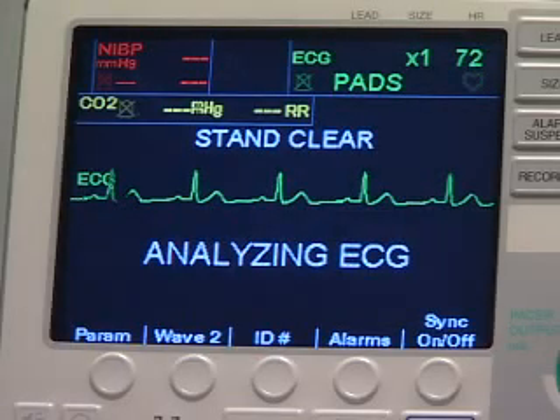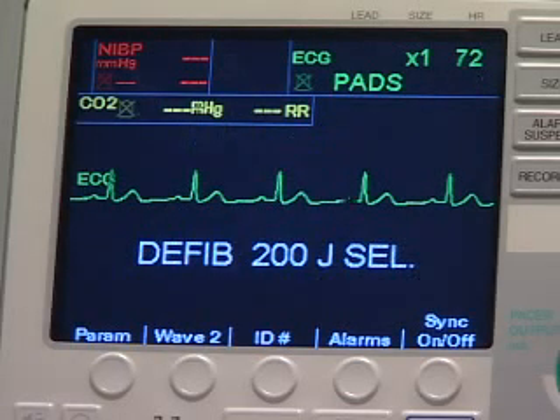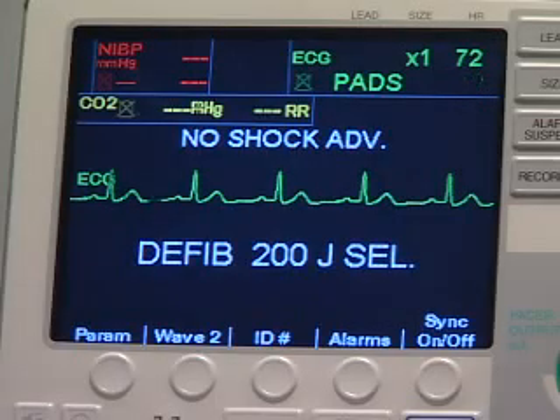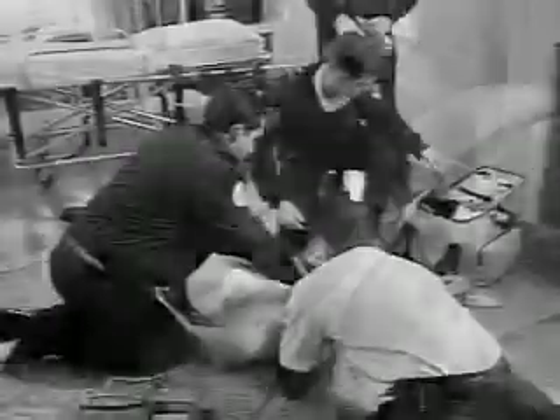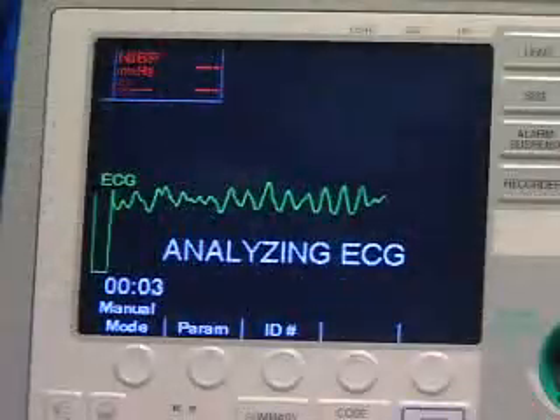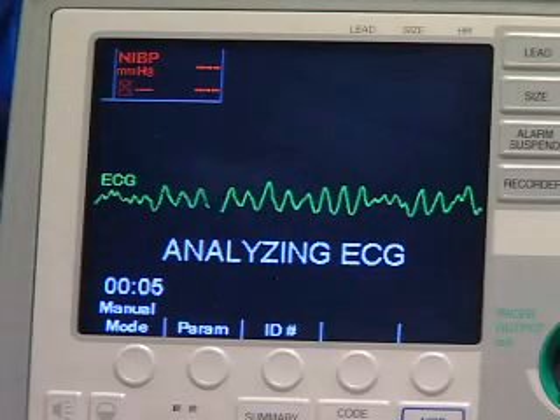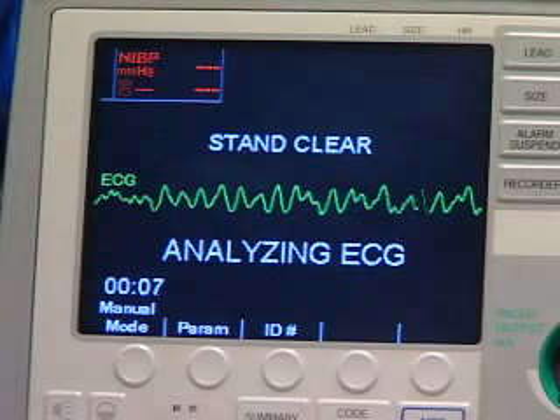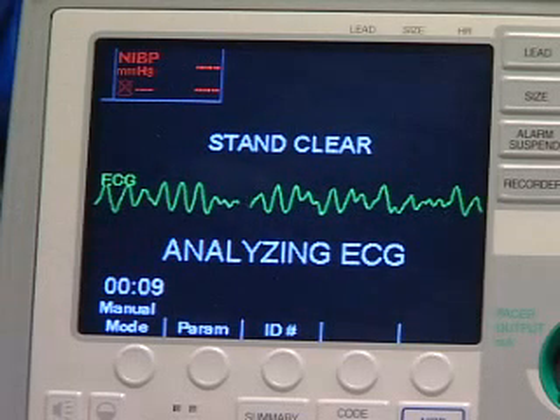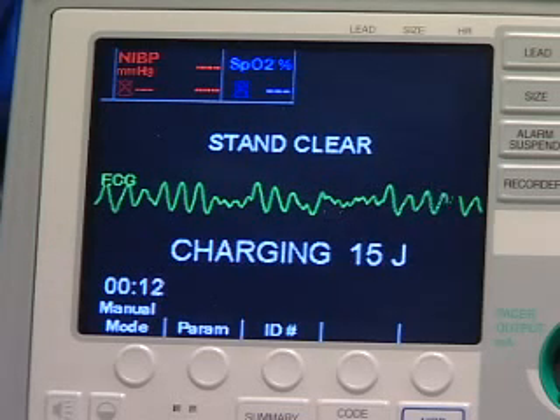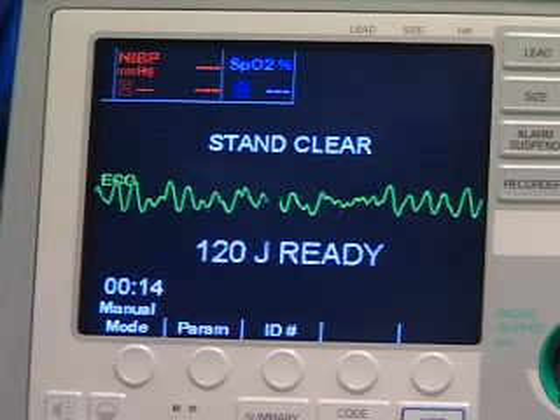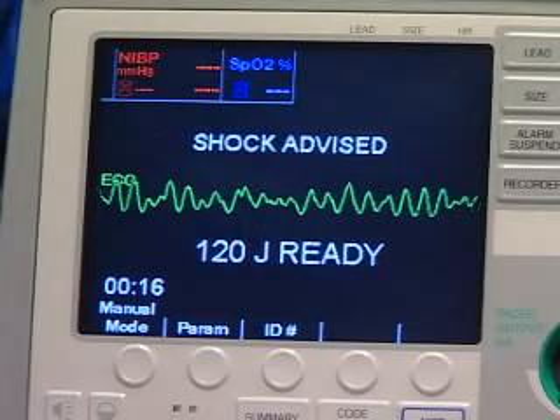When analysis is complete, the unit indicates whether or not a shock is advised. No shock advised. When a non-shockable rhythm is detected, the "No Shock Advised" message and voice prompt is issued. Immediately check the patient's pulse and breathing and resume treatment according to your protocols. If so configured, the defibrillator will automatically begin charging to the pre-selected energy setting and display a charging message. If the patient's rhythm is shockable, the unit will display a Shock Advised message.